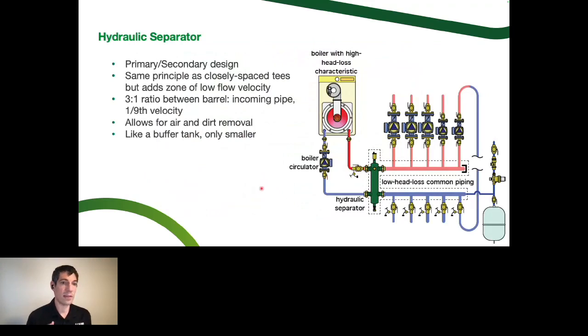There's no secret to how to build a hydro separator. The way to do it right is to have a 3-to-1 ratio between the barrel and the inlets. So if it's a 1-inch pipe connection, that barrel needs to be a minimum of 3 inches. If it's 6 inches, it's just a buffer tank at that point. It's just a very expensive hydro separator that has become a little buffer tank. So I'll go through sizing in a second to show you where that would line up.